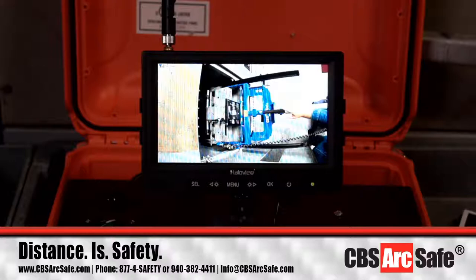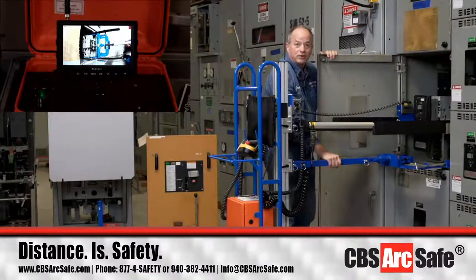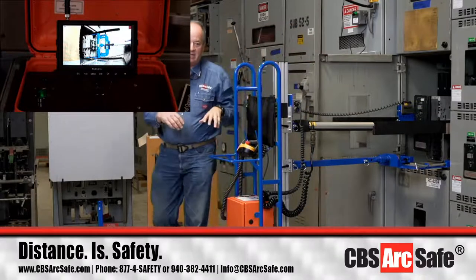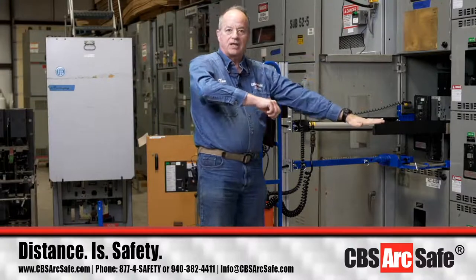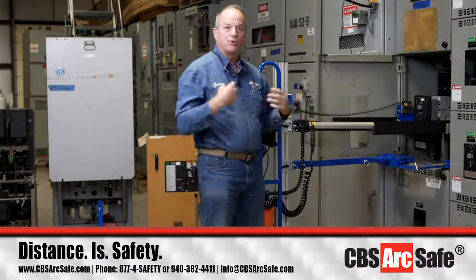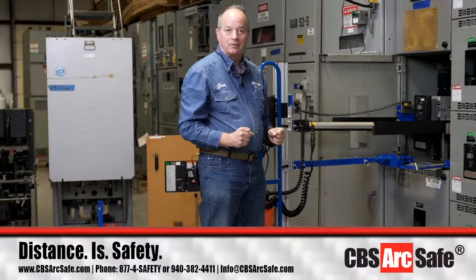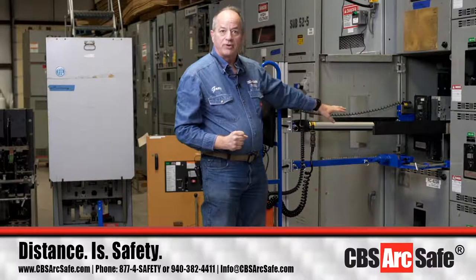That's how this setup works. The bottom part here is what we call a cubicle or cabinet attachment. When a man sets up in front of a DB cubicle, he puts this yoke on, reaches in, pushes down the latch, and yanks. He is the push-pull reference with this yoke to get the breaker in and out of the cubicle. We have to generate a fixed point of reference for the RRS2 to perform this operation.